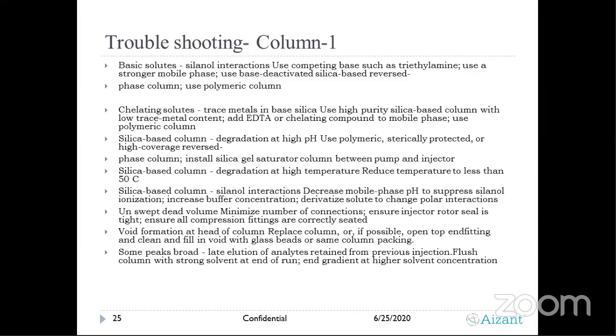Yes, participants, I am back now and we can go ahead with the columns. So hopefully for the other 4 components, you got the essence of what the root cause will be for each component. This is one of the blacklisted items in troubleshooting, I think, from my practical experience. Whenever facing any challenge, people will directly blame the column, whether it's that we are not getting a good peak shape or a wavy baseline. Experts have to come into the picture here, because once you have such challenges in your chromatography, never blame the column. That's why I kept the column last: the first intention during troubleshooting goes to the column, that the column is not working. Every chemist or analyst will come to the head or the supervisor saying the column is not working, but the real challenge exists somewhere else.